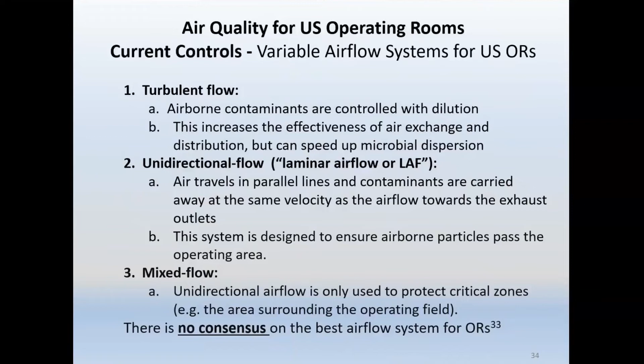Then there's mixed flow, which combines unidirectional airflow used only to protect critical zones, specifically the areas around the operating field. But there's really no consensus on the best airflow system for operating rooms.